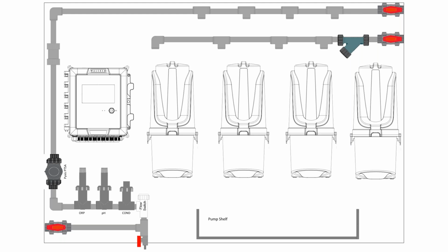Awesome. Another question. Explain how the PTSA correlates to actives when you're mixing in your PTSA fluorescence with your chemistry. So what's the correlation between it? Yeah, it's a couple of different things. The ratio that we utilize in solids is different, because our dosages are typically 4 to 8 times less than what a liquid product dosage would be.